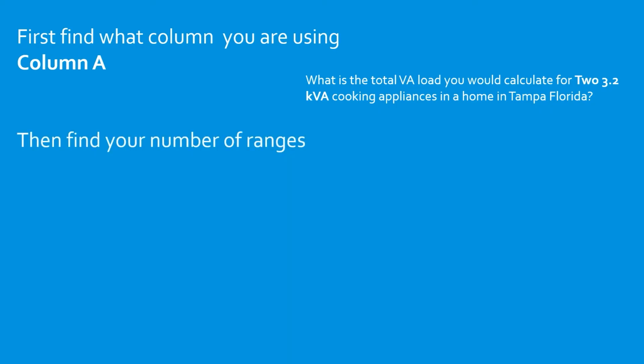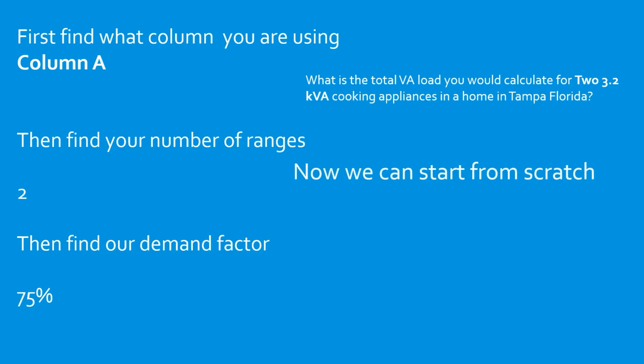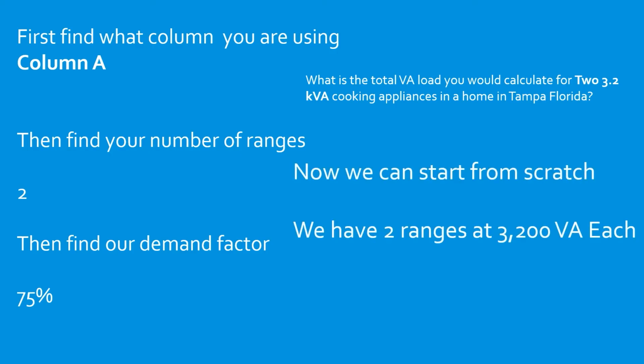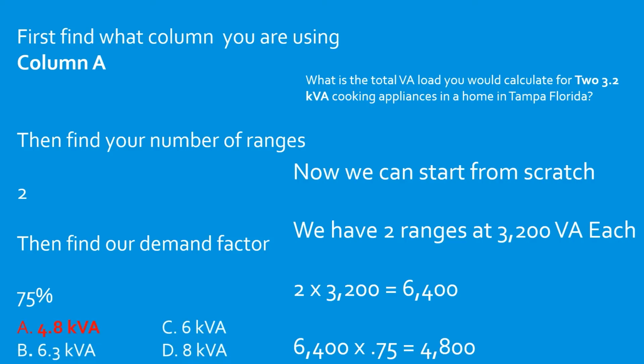Now we're going to find our number of ranges on the left-hand side. We're going to come down and we're going to tee off. So we have two ranges. We're going to come over to column A. We're going to tee off, and we're going to find that our demand factor is 75%. And now we can start from scratch. We take our two ranges that are 3,200 VAs each. We're going to take 2 multiplied by 3,200. That's going to give us 6,400. Now we take that 6,400, we multiply it by 0.75, and that's going to give us 4,800 VAs. And we're going to select A.